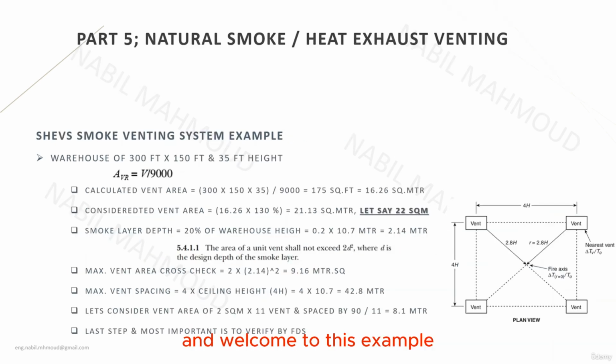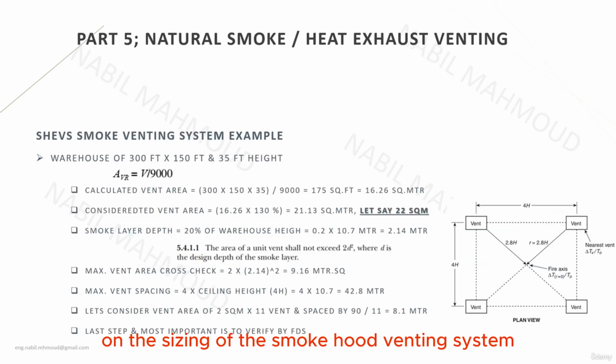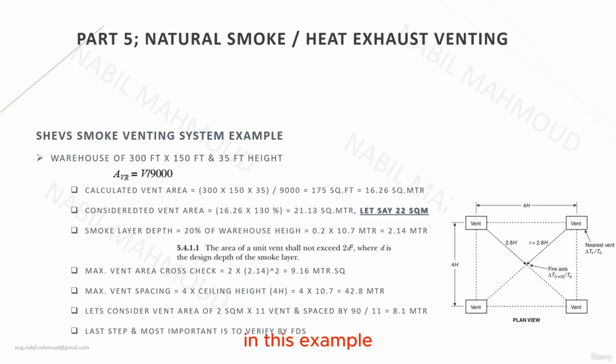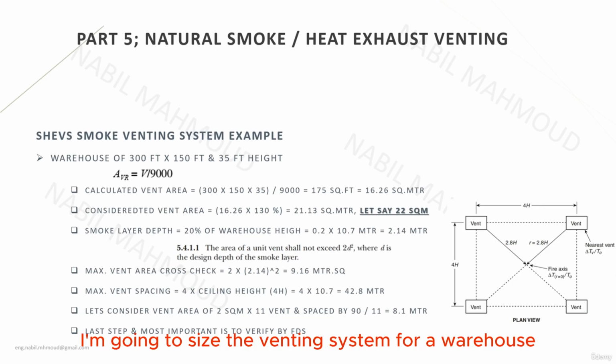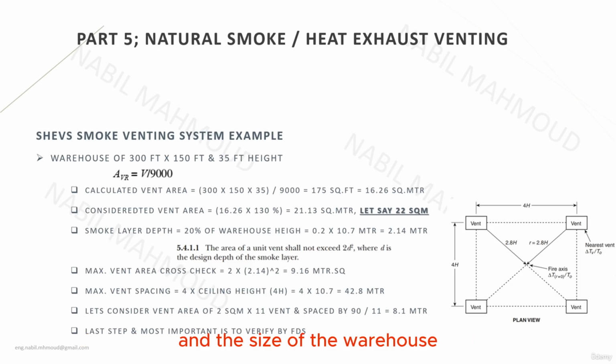Hello everyone, and welcome to this example on the sizing of the smoke heat venting system. In this example, I'm going to size the venting system for a warehouse, and the size of the warehouse I'm considering is 300 feet in length by 150 feet in width by 35 feet in height.